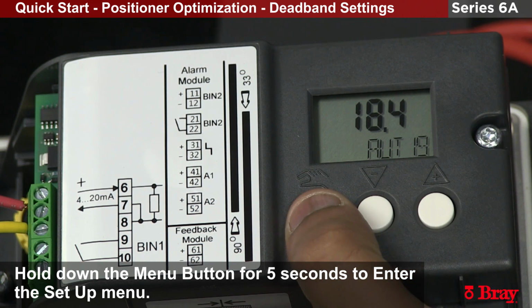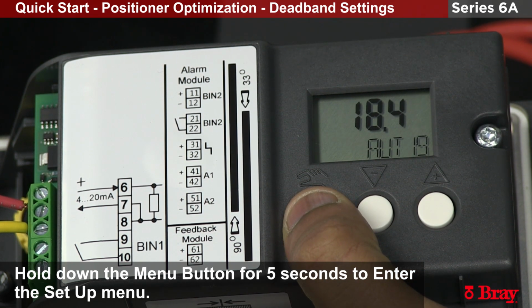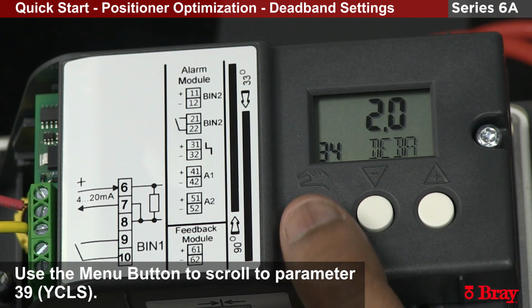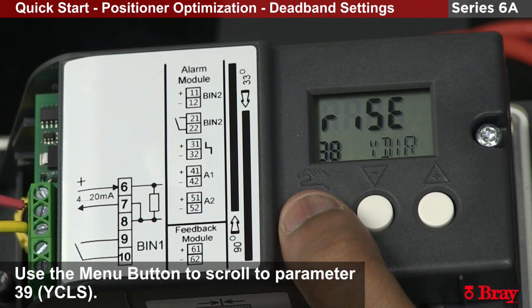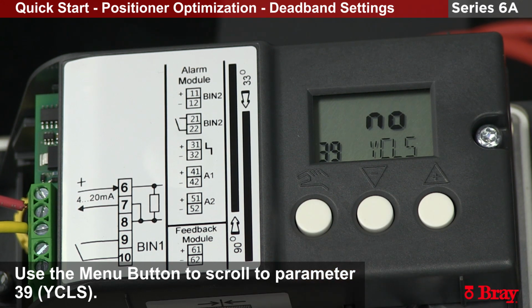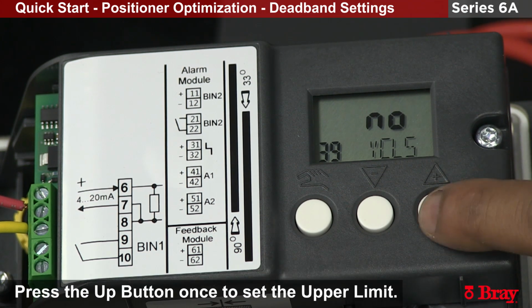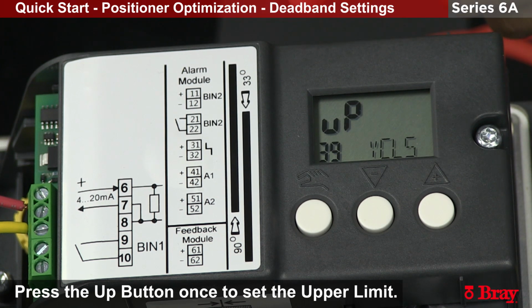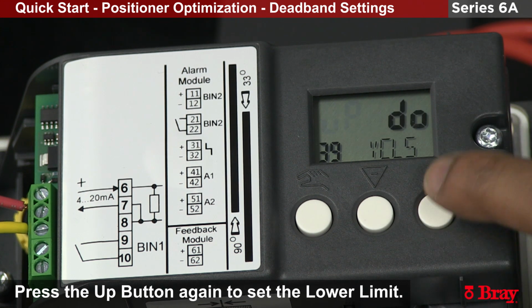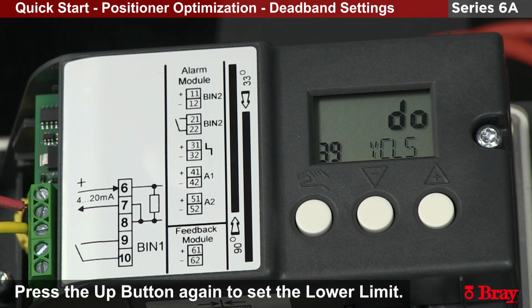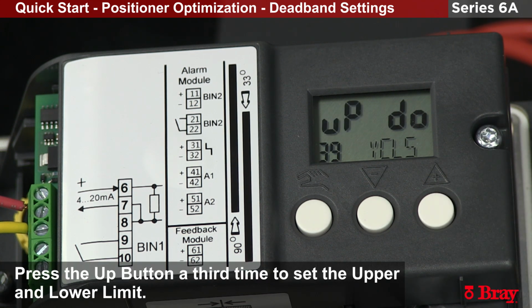So once again, we'll hold down the hand button to come out of auto. And this time we'll go to variable 39. From the factory, it's set to no. If I hit the up button, it'll let us establish an upper limit. This would mean you'll ignore loop power at a certain degree in the open section. If I hit up again, we'll bring up do. That'll just be for a lower limit. Up again, we'll do an upper and lower limit. In this example, we'll do both.